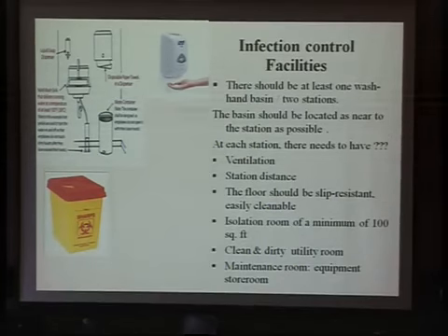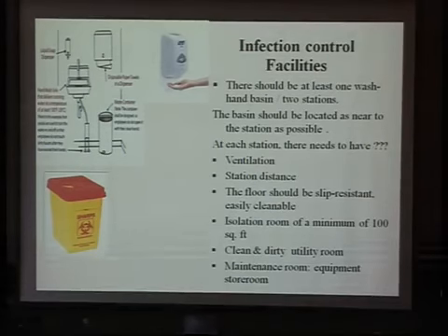The ventilation. Ventilation is very important in every healthcare setting. For the hemodialysis unit, the rate of ventilation differs if it is under reconstruction or renovation, or already settled. If there is reconstruction in the unit or around, we should have 12 air changes per hour, ACH. But if it is already settled, just 6 air changes per hour is enough. Okay?